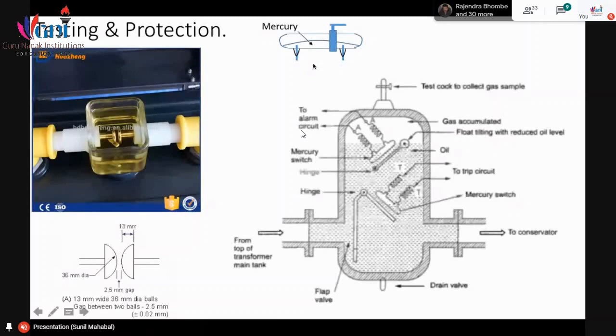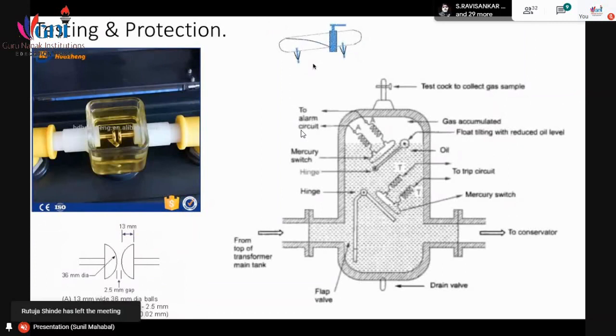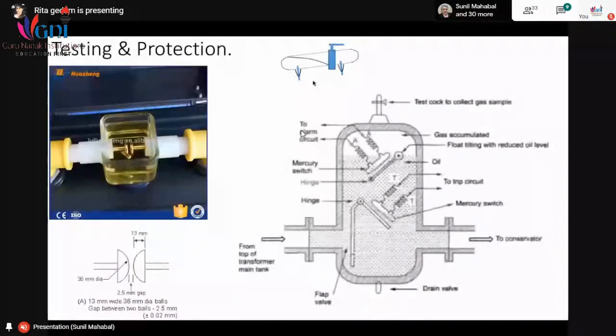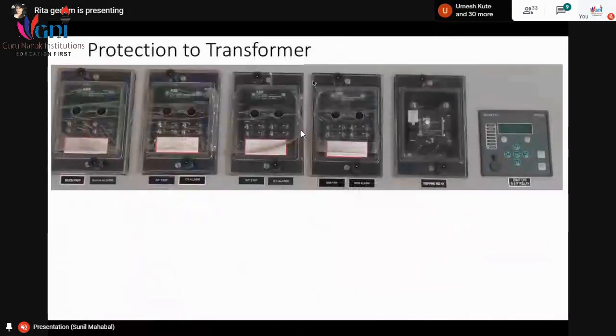But when the oil level goes down, the mercury tube carrying the mercury will tilt because of gravity, because it is hinged eccentrically. It is not in the center, it is eccentric. So it will tilt, and then the probes will open. That is how the mercury switch works. There are ample applications for this mercury switch, in machine control also. So this is how it works, and this is the protection given to the transformer. These are the various protections.